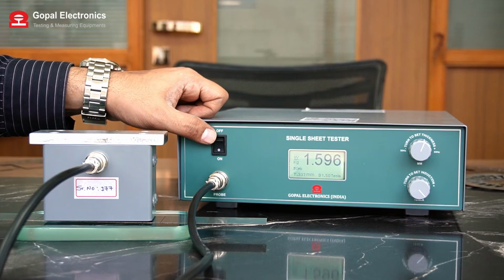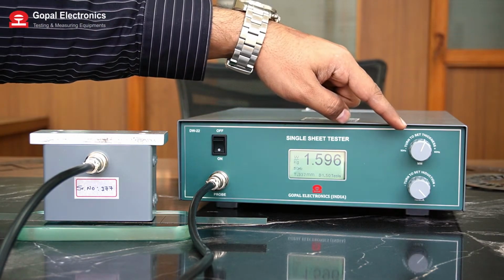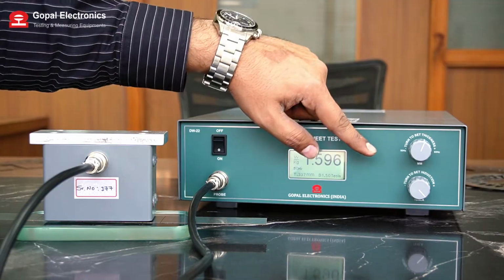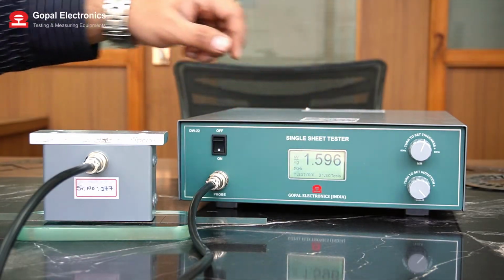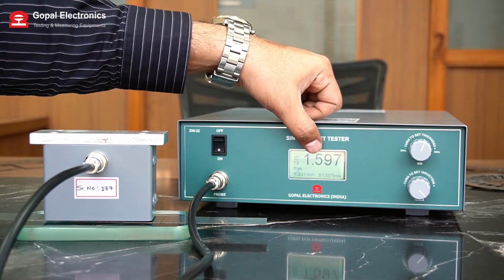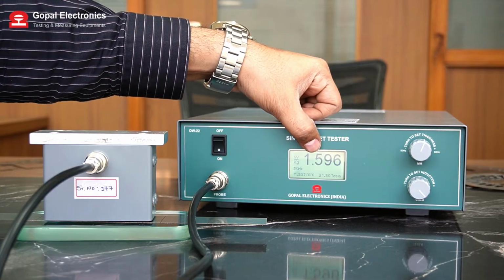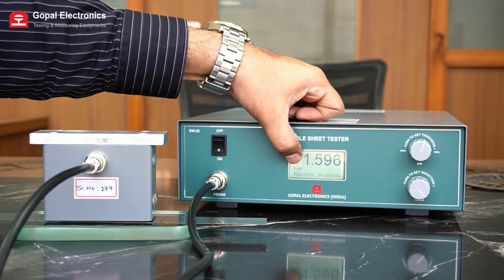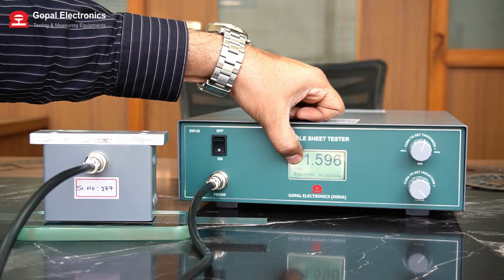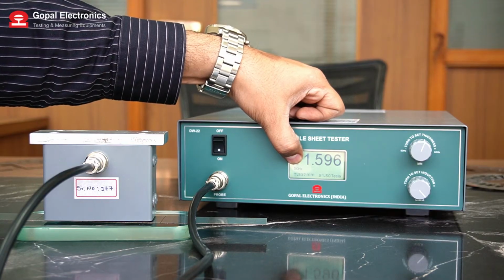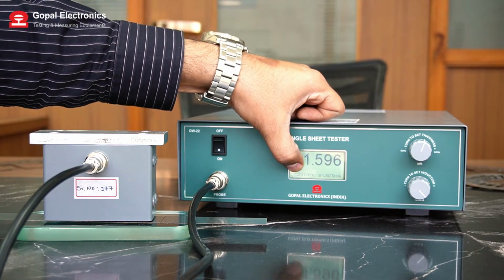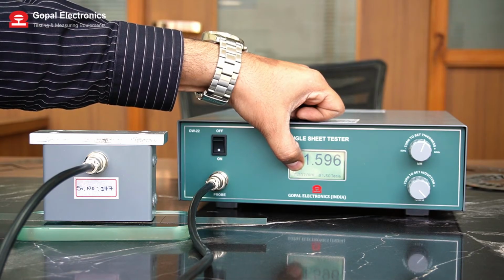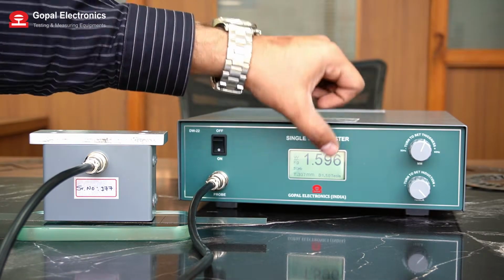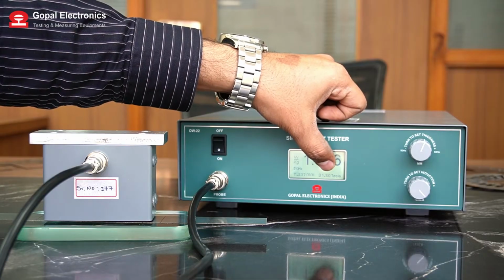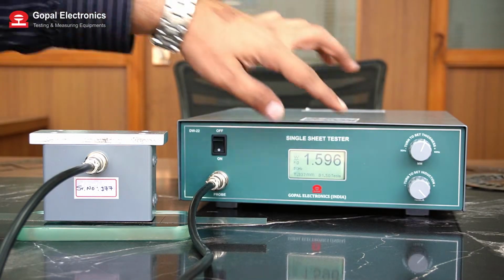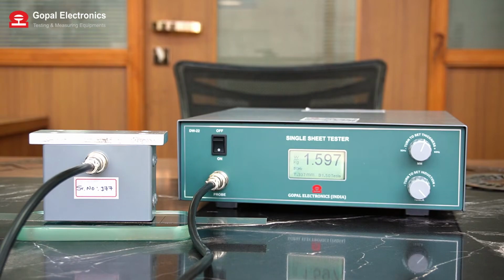This is the on off switch. This is the knob to set the thickness. This is the knob to set the induction. Here you can check the result of watt per kg, which is the final reading. Here you can see the frequency in Hertz, 50 Hz right now. Below is the thickness of the sample, you can set through this knob. This one, B1.5, is the induction in Tesla, you can set through this knob.